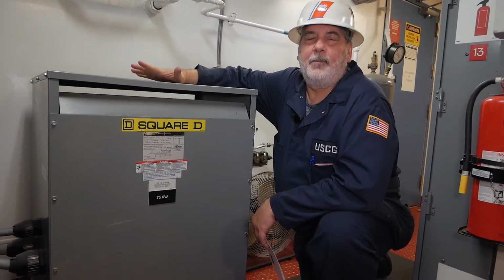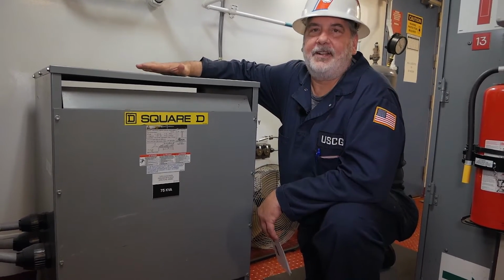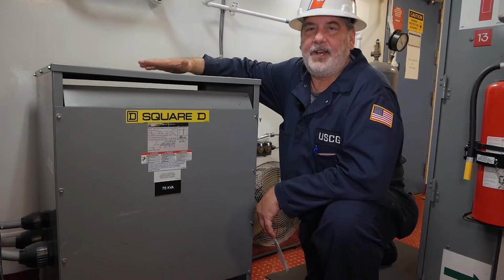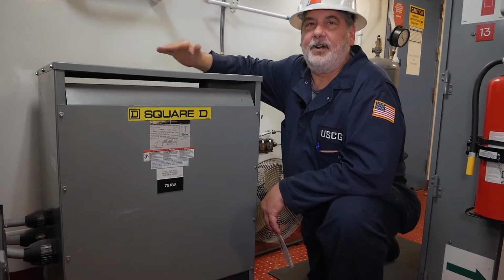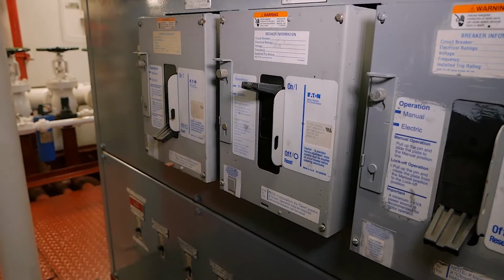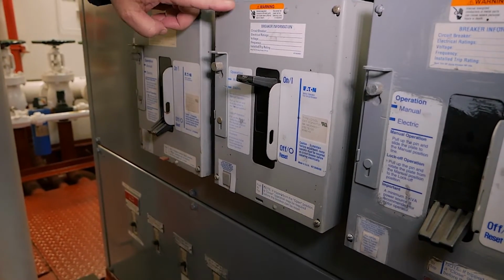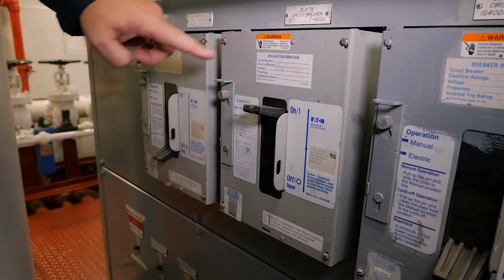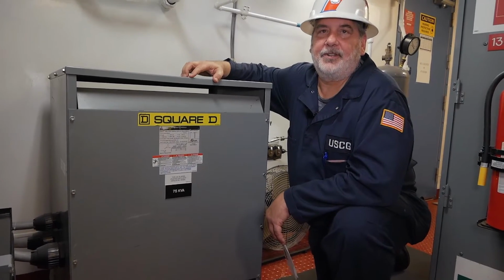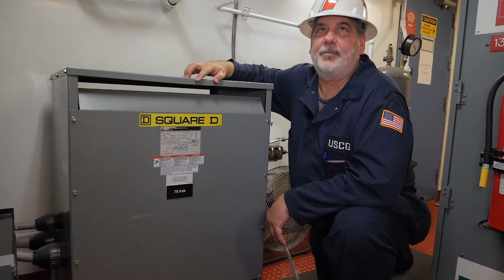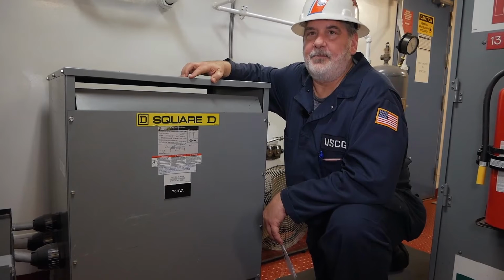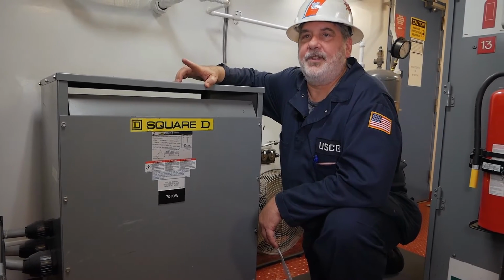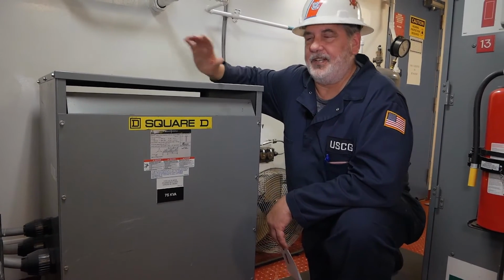And with transformers, we also must keep in mind that they have to be powered or fed by a circuit breaker for overcurrent protection. On the switchboard, you'll see the circuit breaker for this transformer. You have to make sure that they are protected by circuit breakers. Occasionally you may find one directly wired without overcurrent protection, and again, that can be dangerous.